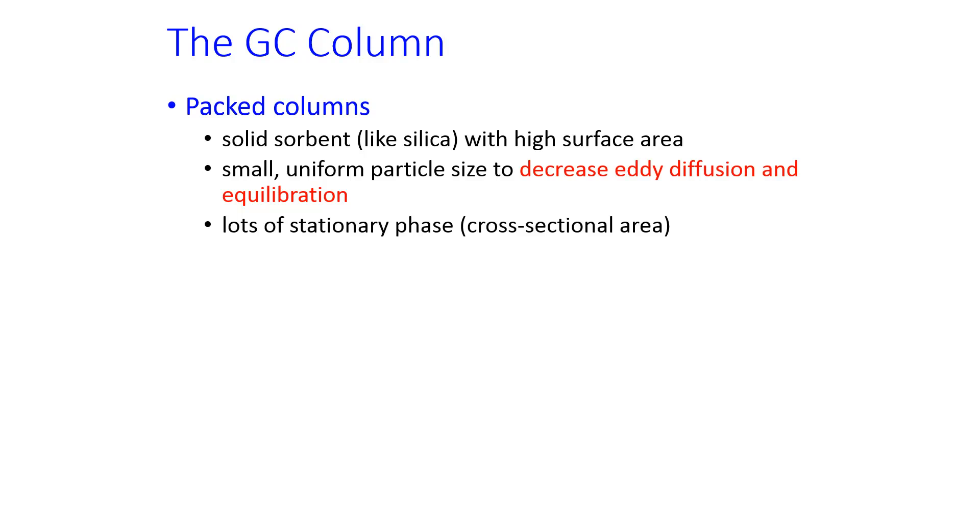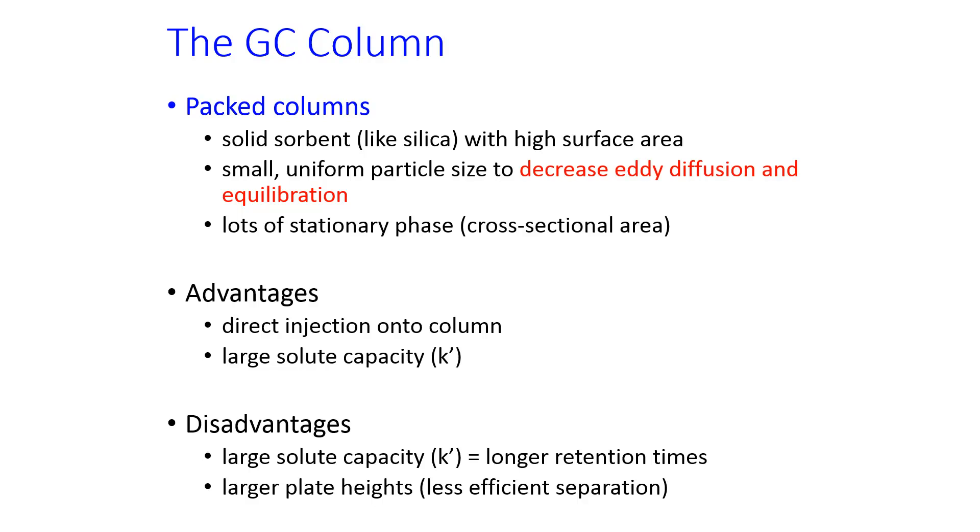These silica particles should be small and uniform to decrease processes that we'll talk about later that can lead to band broadening. The advantages of this is that you can inject directly onto a packed column, and they have a large solute capacity, so they're difficult to overload. A disadvantage is that this large solute capacity comes along with a longer retention time, and they also have less efficient separation.